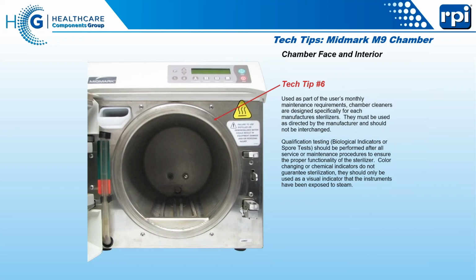So, testing biological indicators. You guys should know about spore tests if you're working on sterilizers. There's a story in spore tests. Spore tests do not check the machine. Spore tests are designed to check the operator, though nobody tells the operator that. If you have a failed spore test, don't immediately jump to there's a problem with the machine. Ask the people running the machine how they did the spore test.